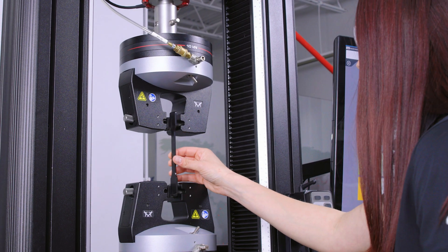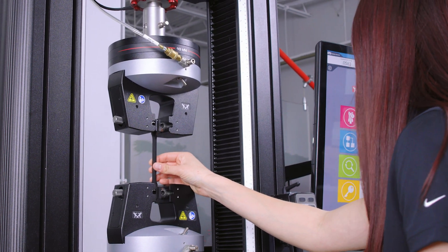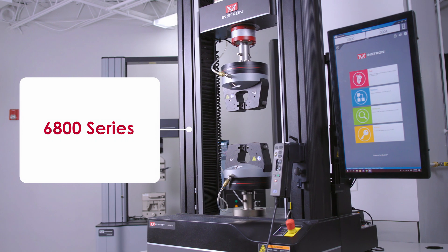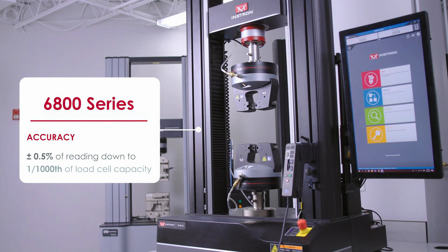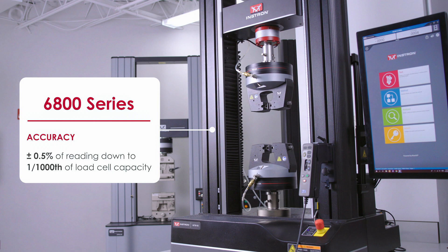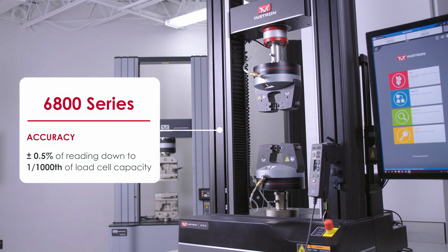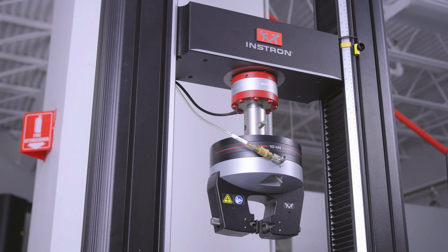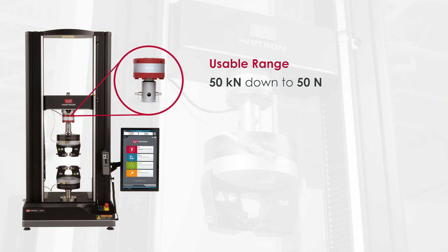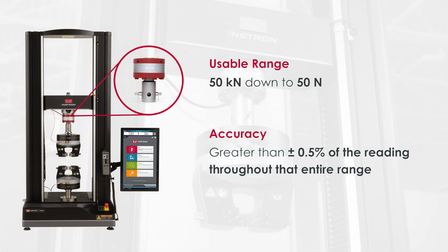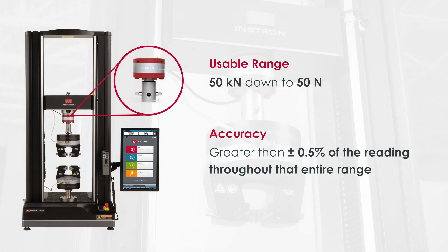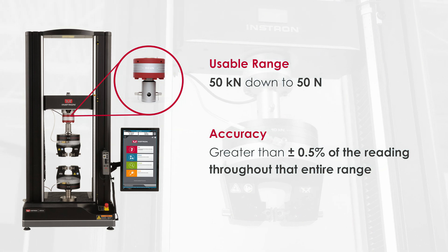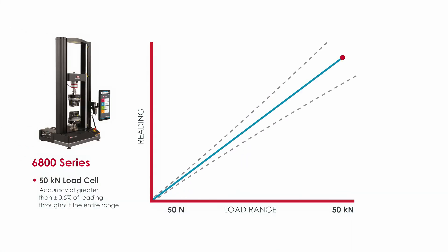Now let's look at a real-world example. Say we have our 6800 series system, which has an accuracy of plus or minus 0.5 percent of the reading down to one one-thousandth of the load cell capacity. Equipped with a 50 kilonewton load cell, this system has a usable range of 50 kilonewtons down to 50 newtons, with an accuracy of greater than plus or minus 0.5 percent of the reading throughout that entire range. At a 50 kilonewton reading, the error would be within plus or minus 250 newtons, and at a 50 newton reading, the error would be within plus or minus 0.25 newtons.